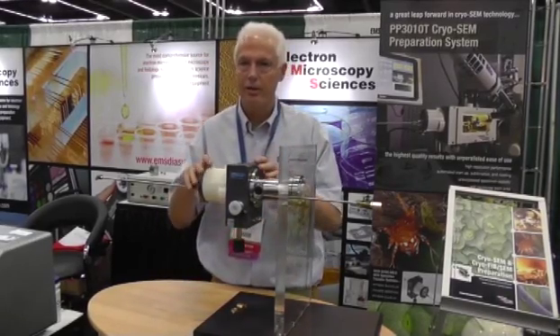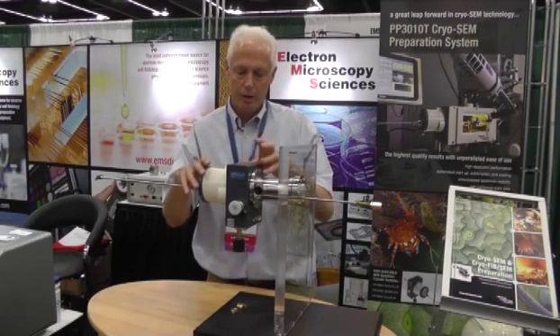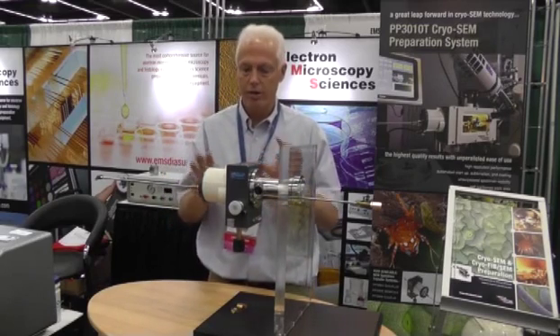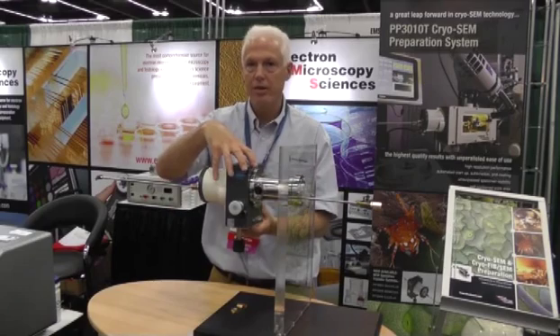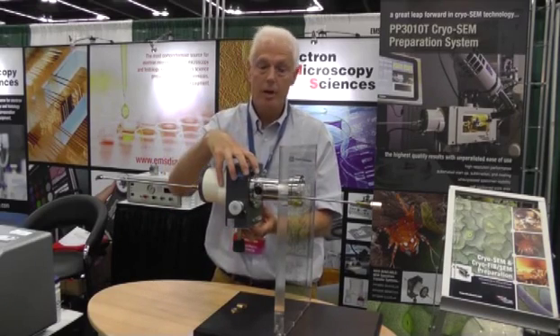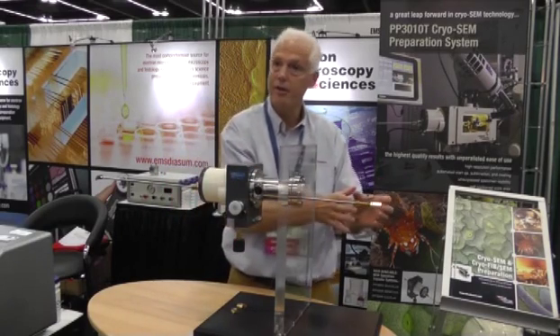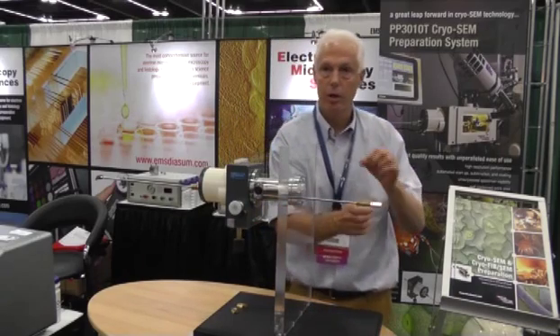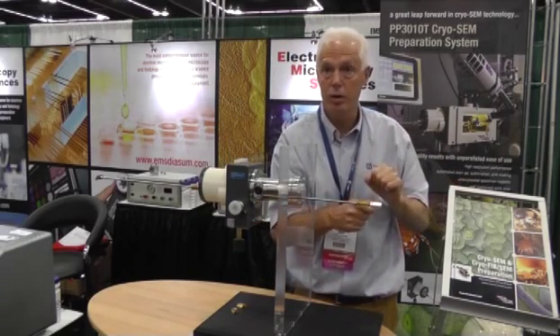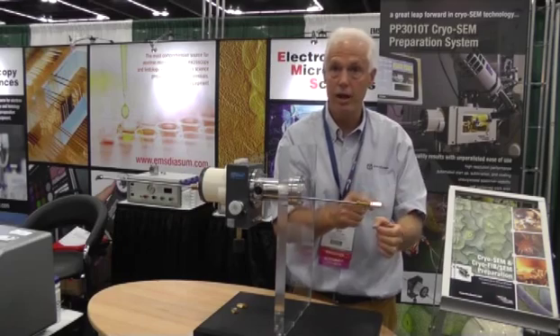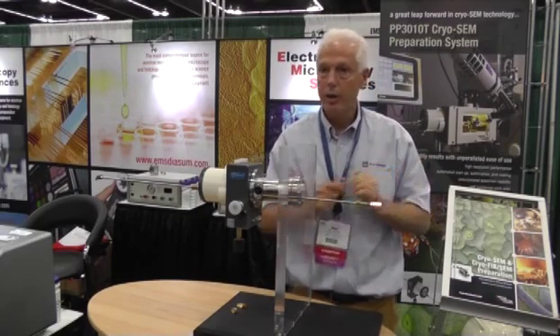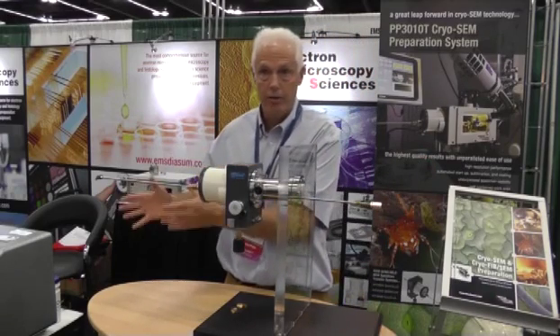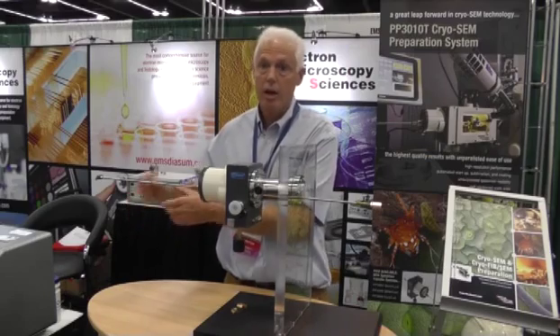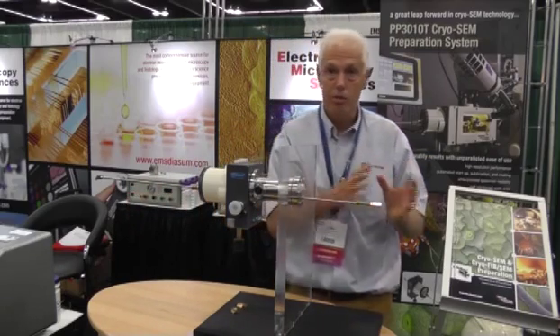The second new product is based around the first, really. This is the CoolLok, which uses the same transfer device and transfer body, but we also have a freezing element inside the microscope. So we have a liquid nitrogen cooled, gas cooled cold stage and cold trap.